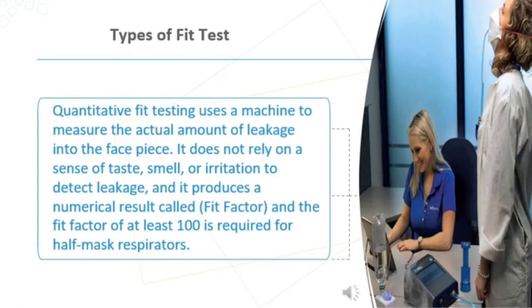The quantitative fit test uses a machine to measure the actual amount of leakage into the face piece. It does not rely on the senses of taste, smell, or irritation to detect leakage, and it produces a numerical result called a fit factor. A fit factor of at least 100 is required for a half-mask respirator. This type of test is objective and depends on the machine.